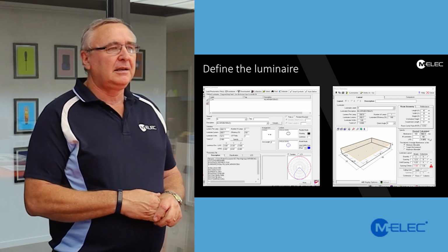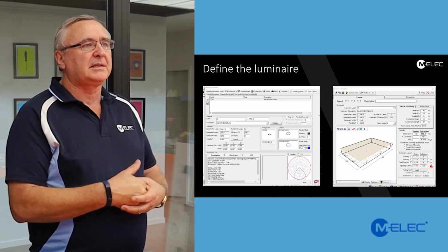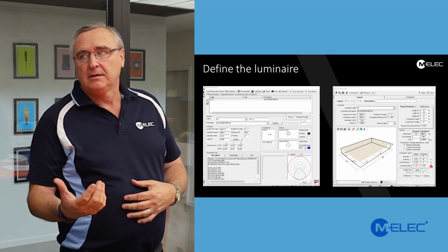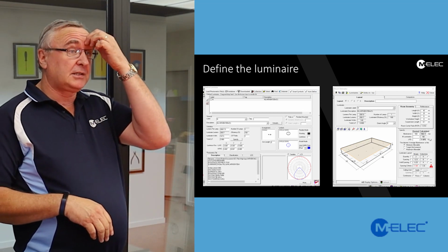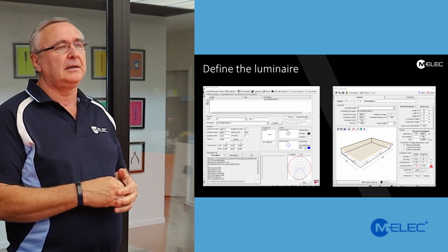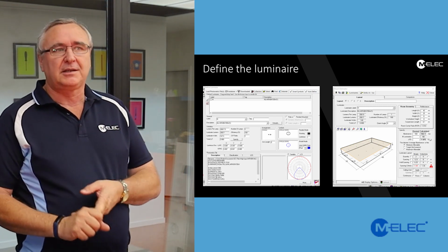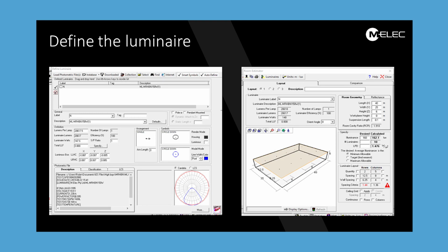Yep. And in this case, this is a room. I've used the room estimator there just to give me a quick example of the amount of luminaires the estimator is telling me that I need to use for a flat roof. Right. Okay. So I put in 160 lux, as you can see there by the illuminance. Yes. And I got that level because the Australian standard for picking, packing, labelling, and warehousing is 160. Yep. So that basically told me I need 10 luminaires, but it did say that the spacing criteria was too far apart. You see it's highlighted in red down there.